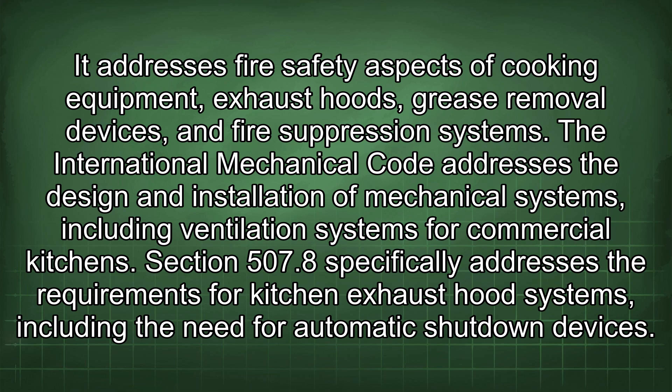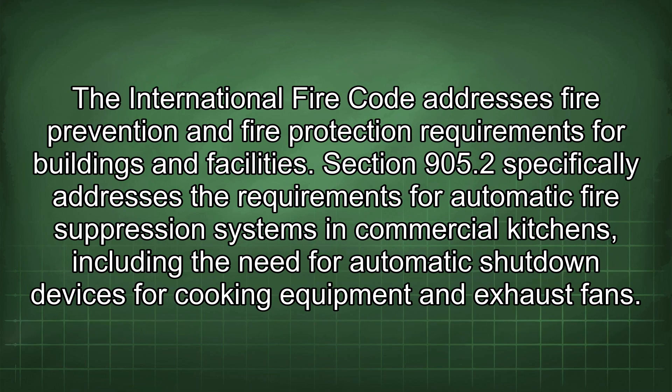Section 507.8 specifically addresses the requirements for kitchen exhaust hood systems, including the need for automatic shutdown devices. The automatic shutdown devices required by these codes are typically activated by a fire alarm or detection system.